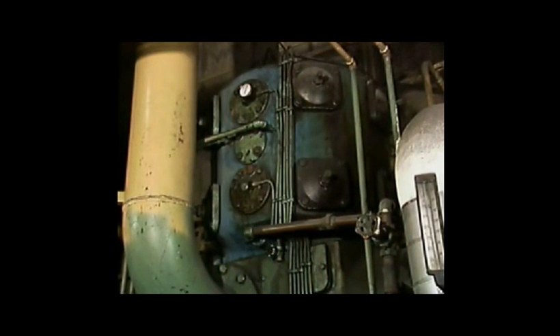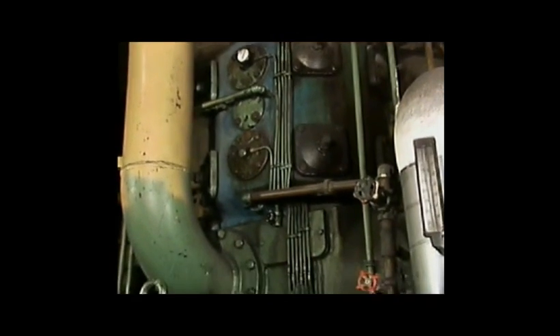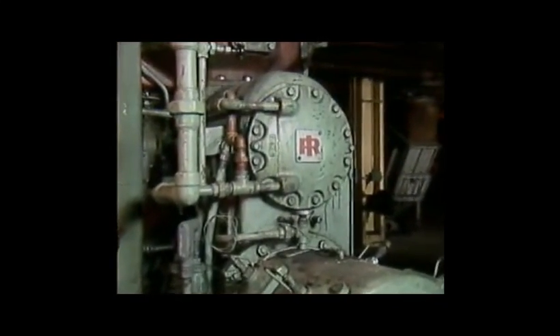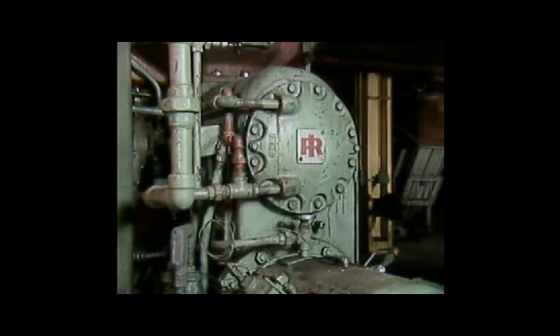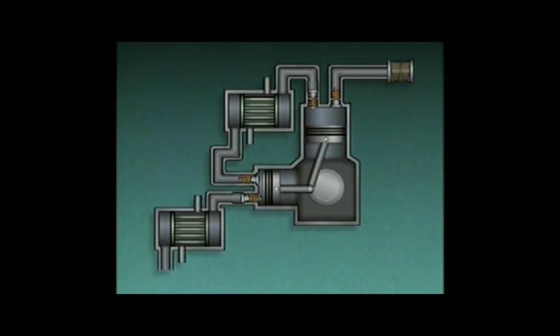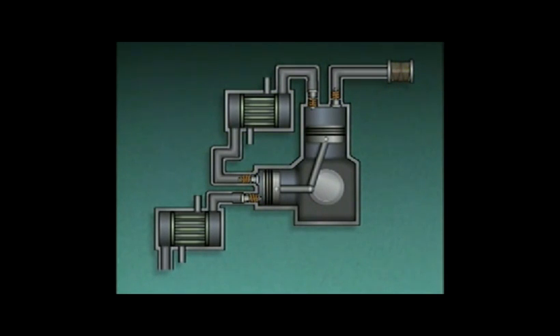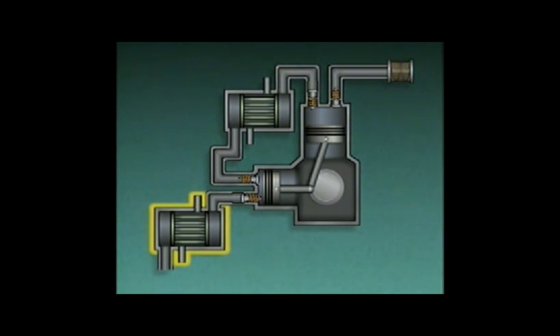Water cooling can be accomplished in two ways. One way is to use jackets — a chamber that surrounds the compressor — through which water is circulated to cool both the compressor and the gas inside it. The other method cools just the compressed gas using one or more shell and tube heat exchangers. Depending on their location, these heat exchangers are classified as either intercoolers or aftercoolers. Intercoolers are generally used with multi-stage compressors and are located between the stages, while aftercoolers cool the gas after the compression process is complete.